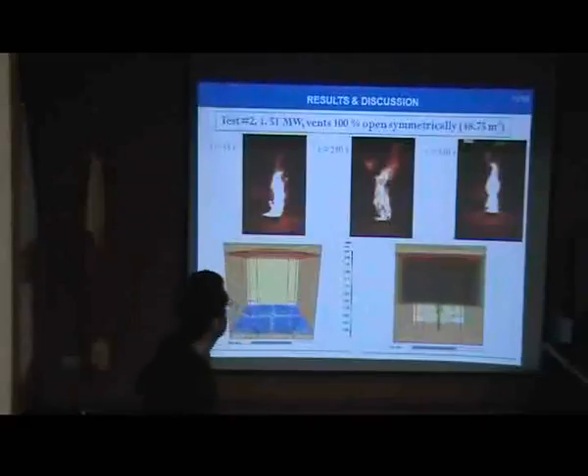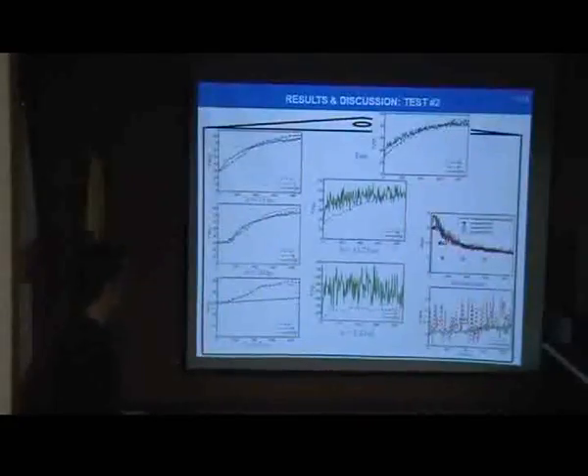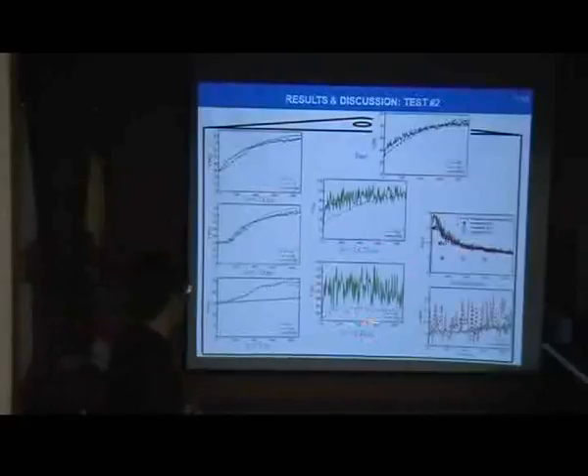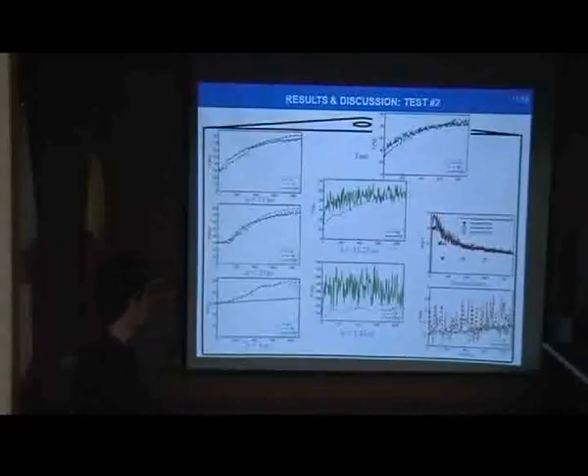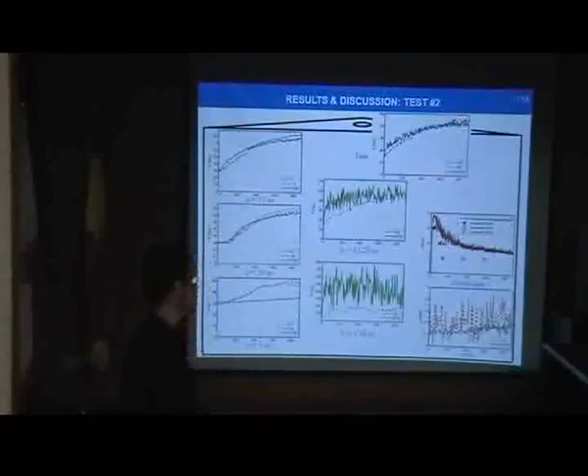Now, we analyze quantitatively the results. Again, FDS over predicts the temperature near the flames, although the differences are much lower, being in the range between 50 and 100%. And at the upper parts, all over the domain, the agreement is really good, with differences lower than 8% all over the domain.